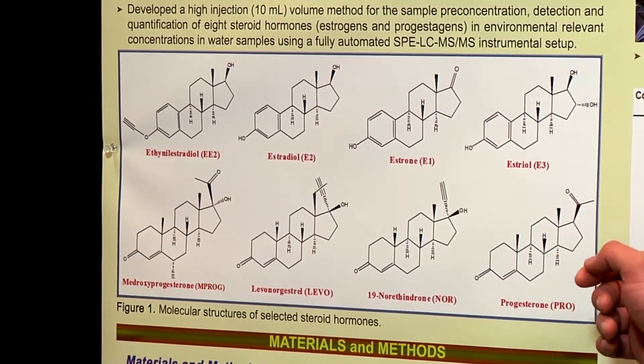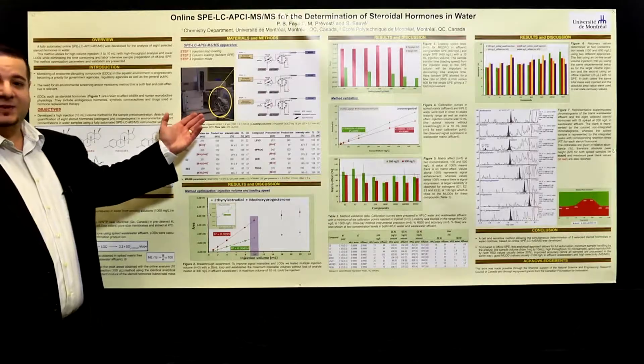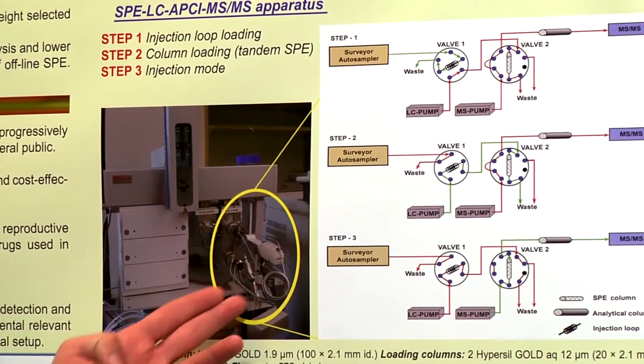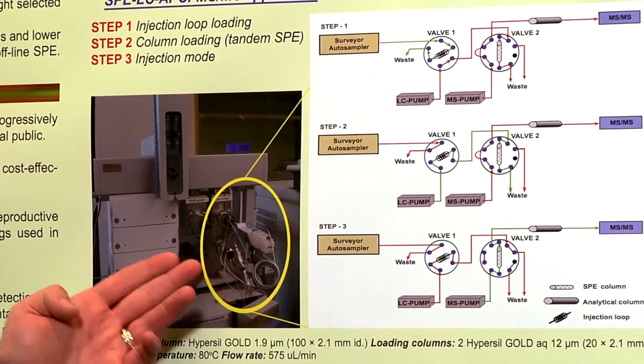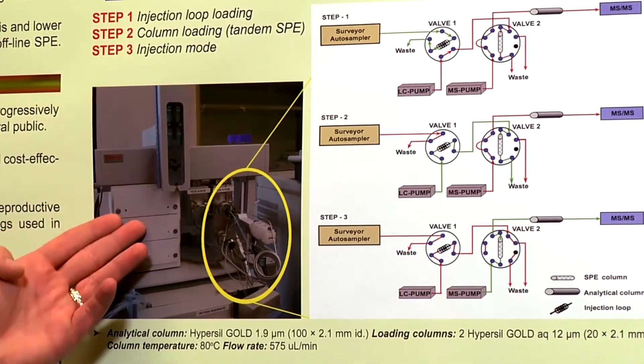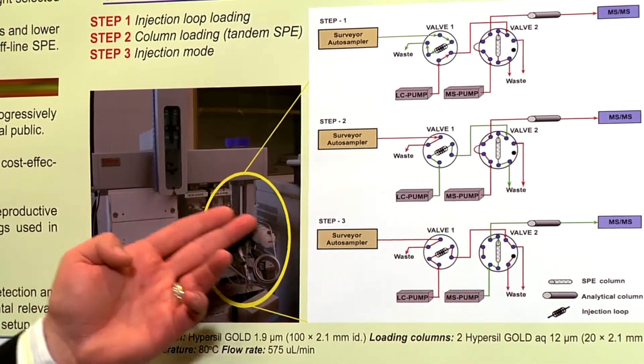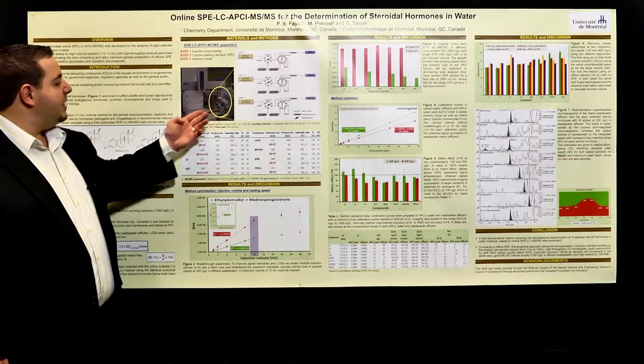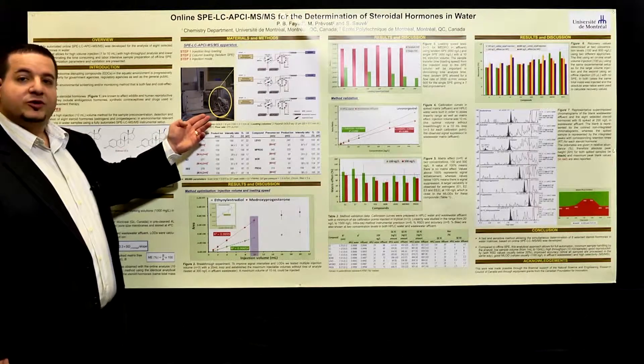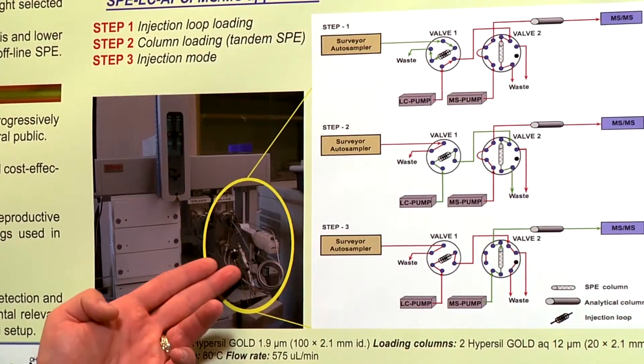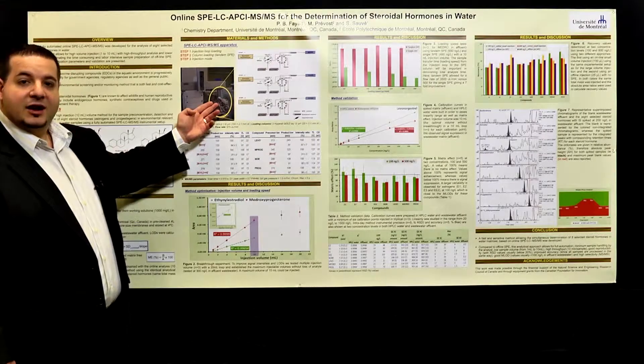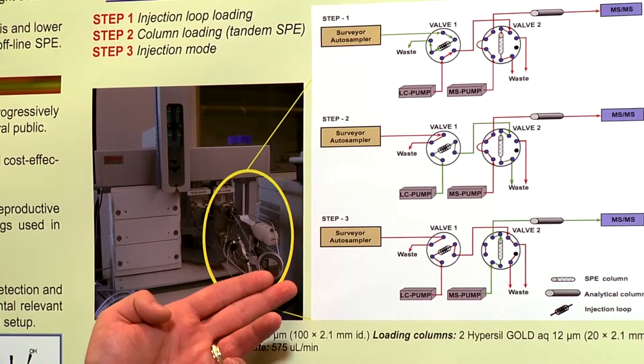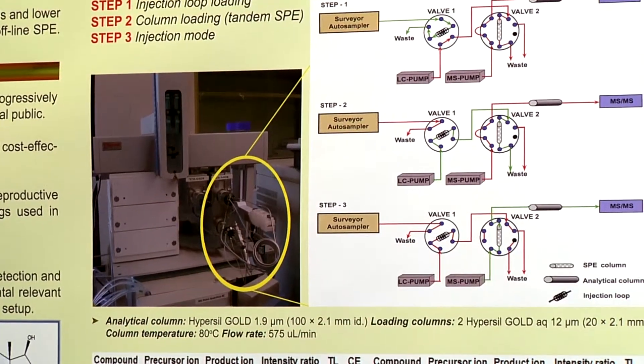We'll be analyzing these by the online SPE method. We have a 10 ml injection loop and online SPE cartridges. The idea is to pick up a volume directly from our sampler, fill the 10 ml loop, and by back-flushing with the LC pump, bring our wastewater into the SPE cartridge where we concentrate our analytes. Once that's done, the MS pump does a back-flush, pumps our analytes out of the SPE cartridges, through the analytical column for separation, and then to the detector — the triple-quad.